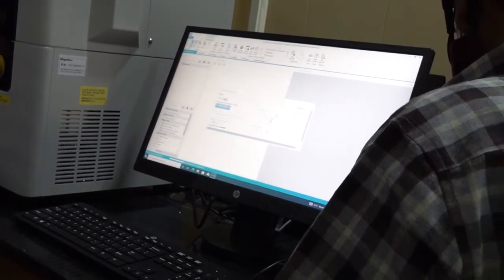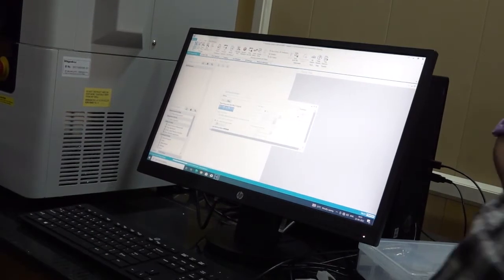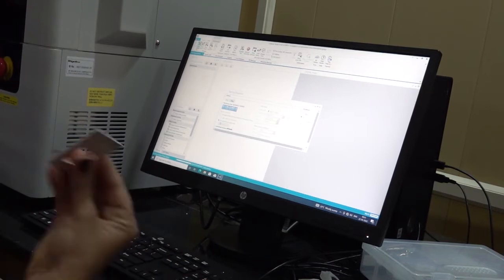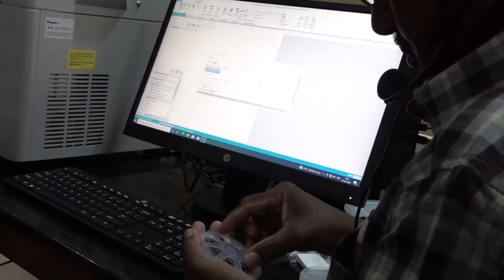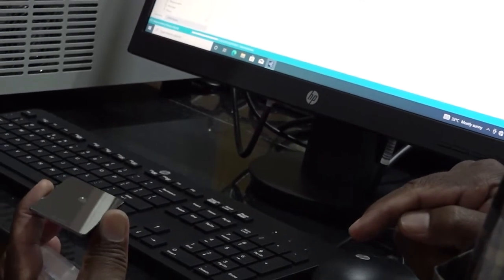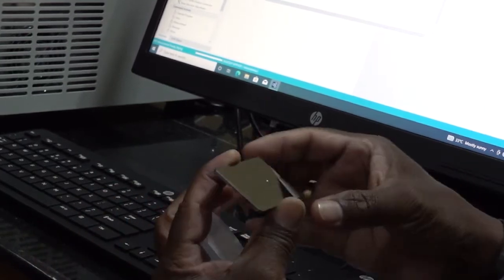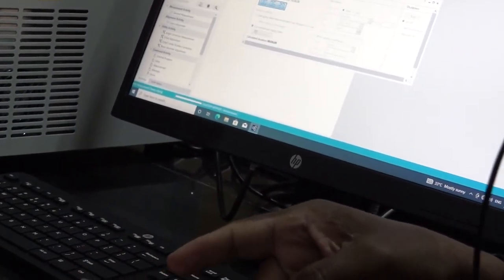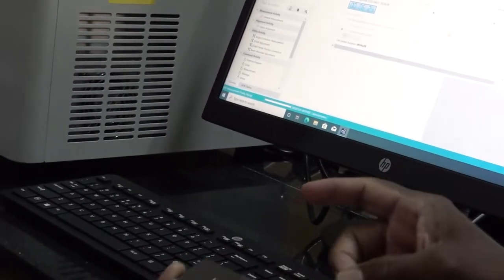Suppose you still have a small quantity, one more sample holder is there. This is called a low background sample holder. See, the background will be very low in this sample holder. So if you have a very small quantity of sample, you can fill it in this. Will this work for liquid samples? No, only powder samples. But when it is this small a quantity, you have to make the divergence slit narrow. Now it is 10 mm. I think this one is maybe 5 mm or 3 mm. A 2 mm divergence slit you have to put there.